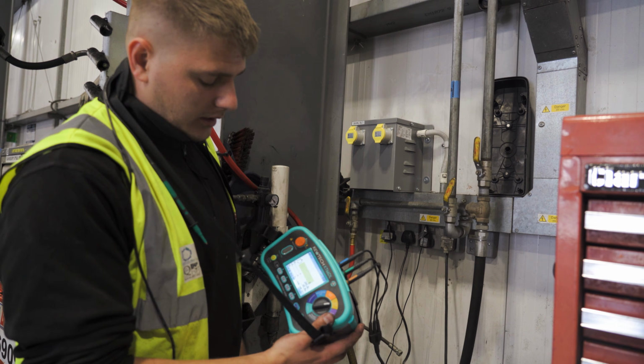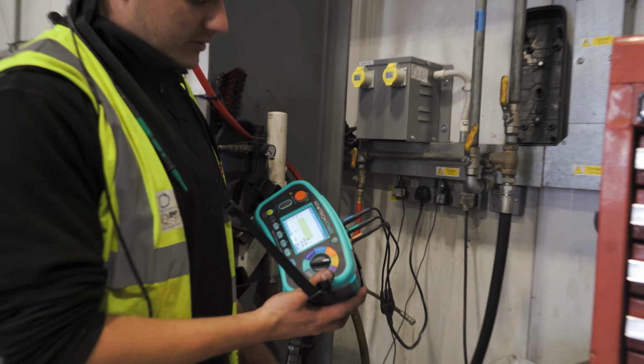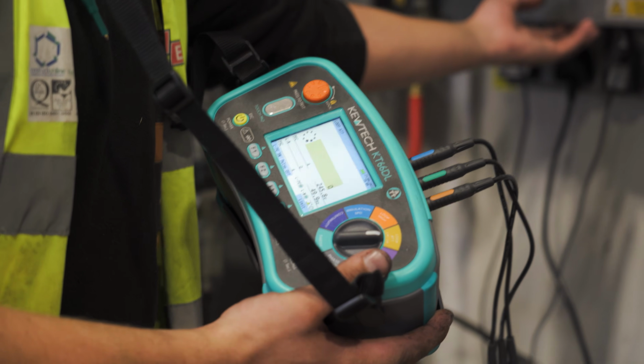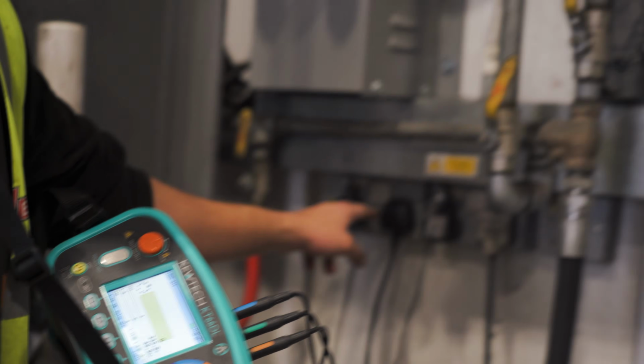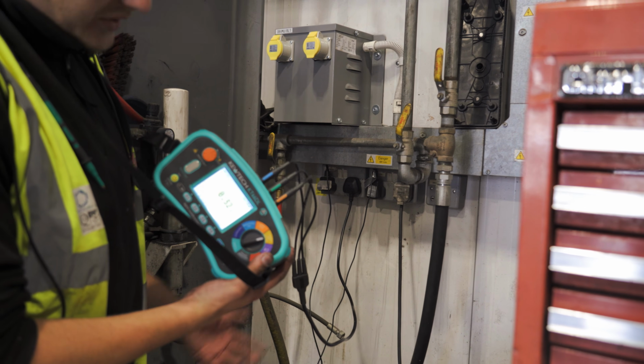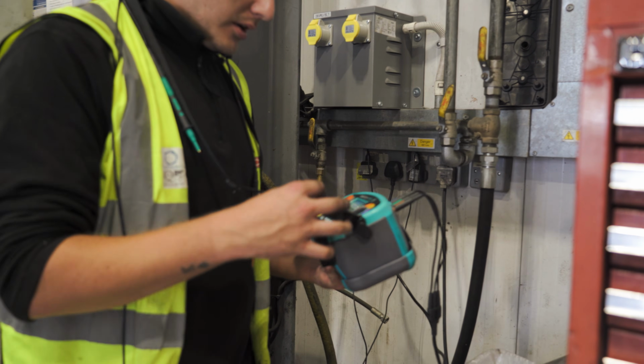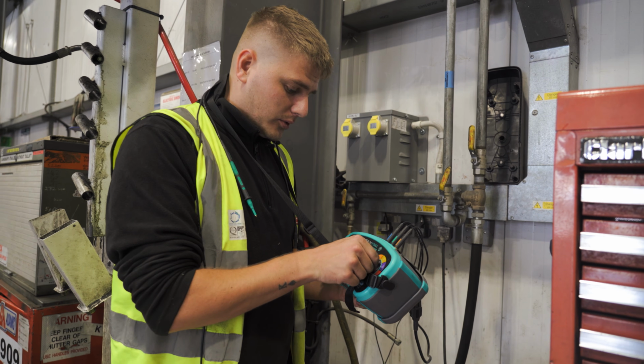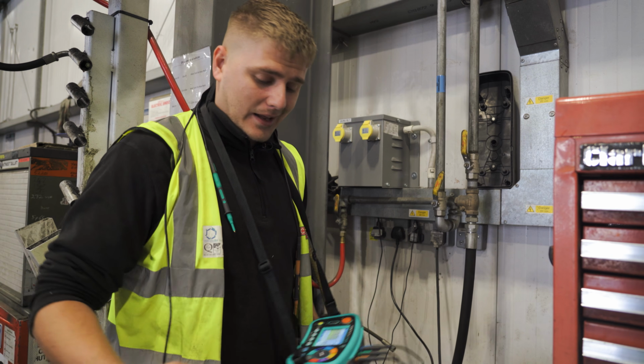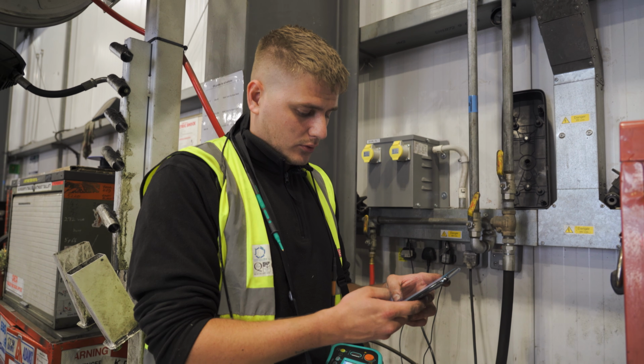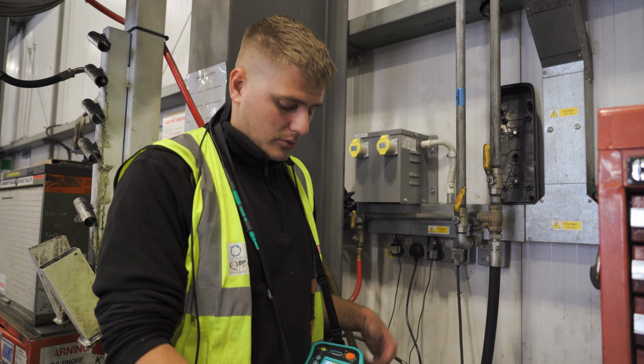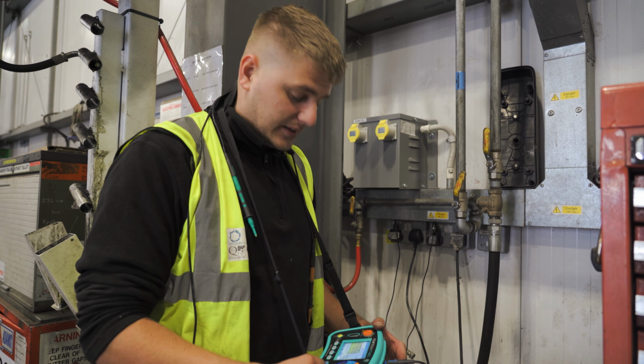Right, so I'm just doing the first of my ZS's, using this plug here. I've had the trunking lid off just ever so slightly. Turns out this is end of line of the same circuit, and that's 0.32. I'm now going to jump onto RCD mode - let's write that down though: 801, 0.32, cool. And then we're going to do an RCD test on auto.